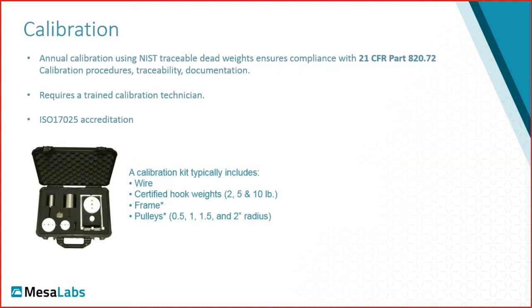So I could even see users calibrating their machines every 1, 2, or 3 years, if in the interim they incorporate verification, which I will talk about a little bit later. It's important to mention that the calibration process requires a trained calibration technician. And our company in Mesa has an ISO 17025 accredited calibration lab, so if you require calibration, we can provide it for you.